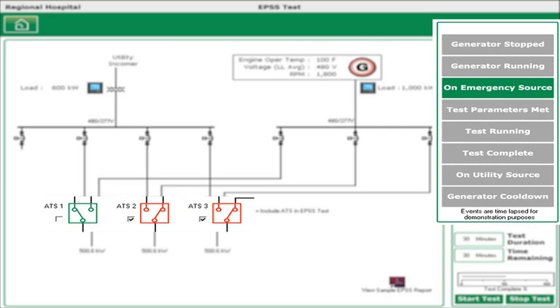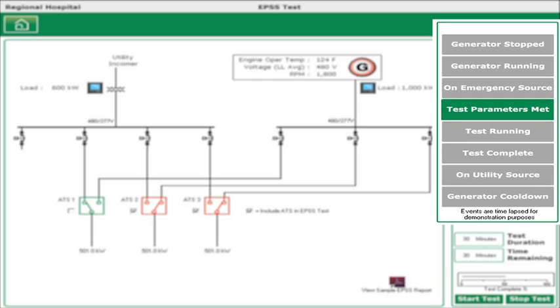Once the generator is ready to accept the emergency load, the ATSs switch the load from utility feed to generator. Depending on the current situation in the hospital, some ATSs can be excluded from the testing scenario. The actual test timing starts when the generator has reached its required operating conditions, which could be load, temperature, or a combination of parameters.